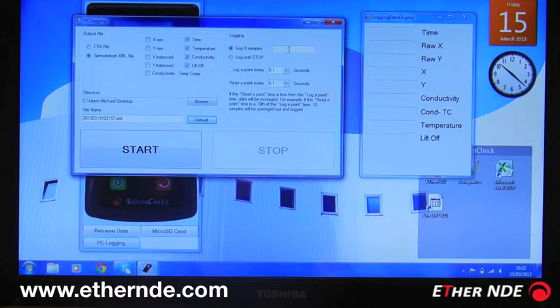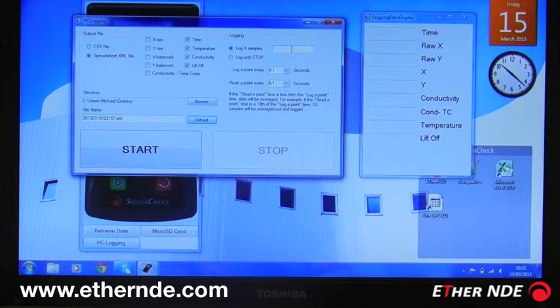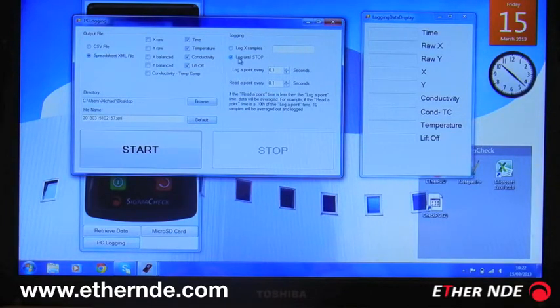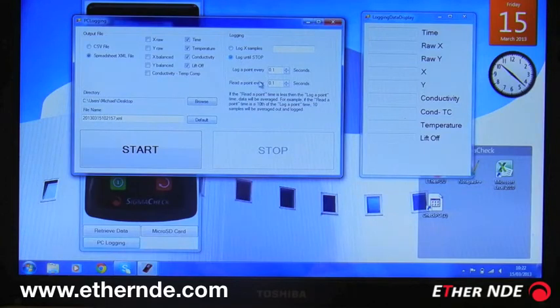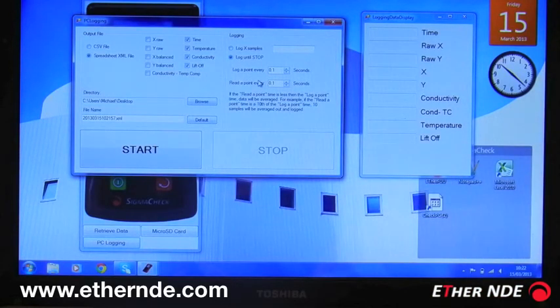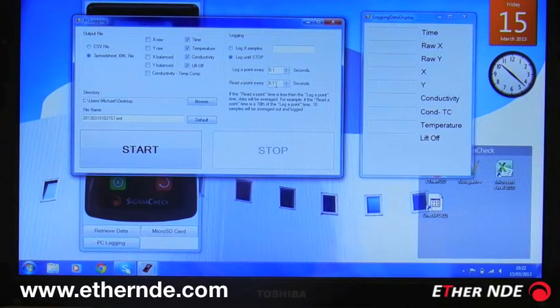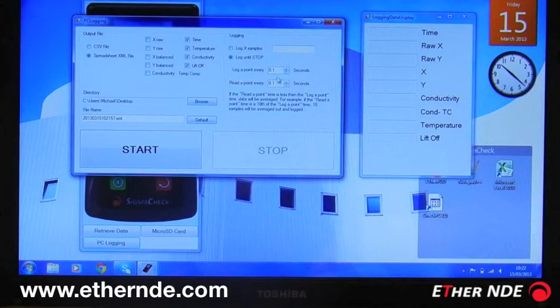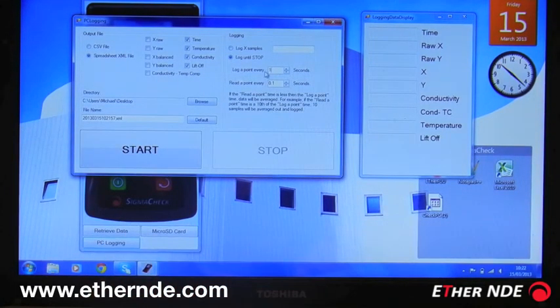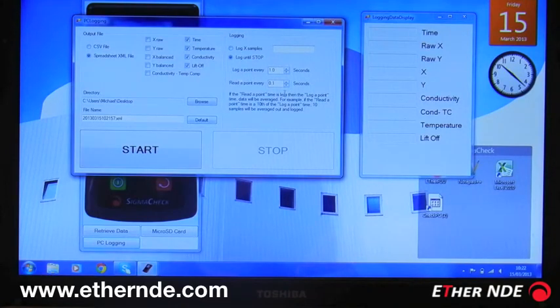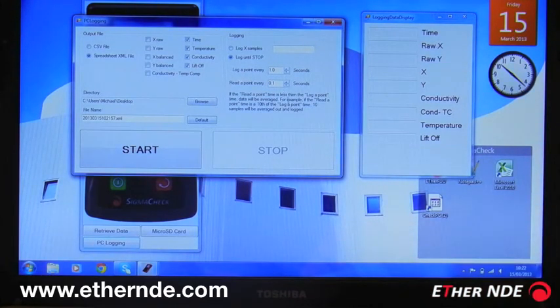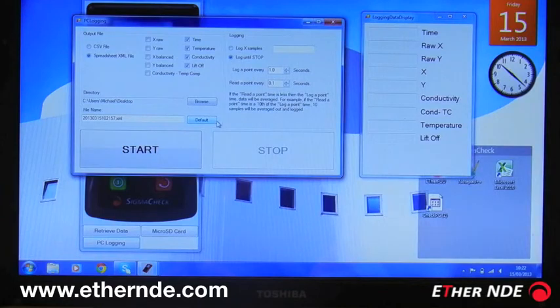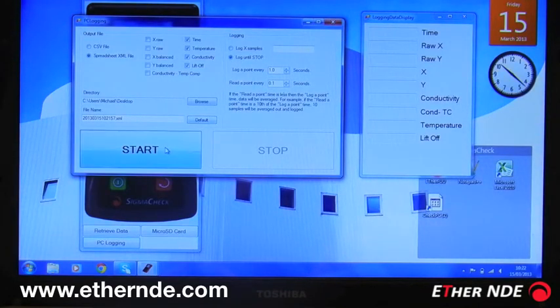So that's what we're going to log and where we're going to log it. Now we can specify a particular number of samples to log and then stop, or we can select log until stop. We then have two other values here: how often we log a point to the file and how often we read a point. If I leave read at 0.1 seconds but log every second, then there will be 10 readings for every one logged, so an average of 10 points will be stored—a basic form of filtering.